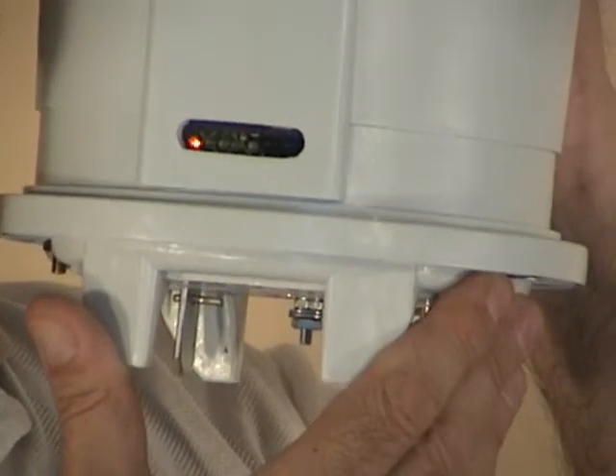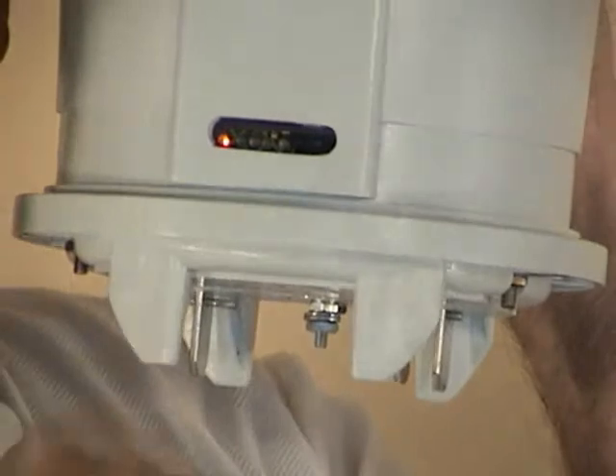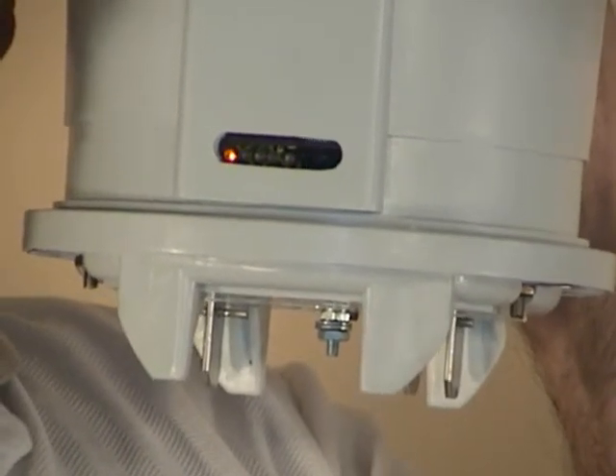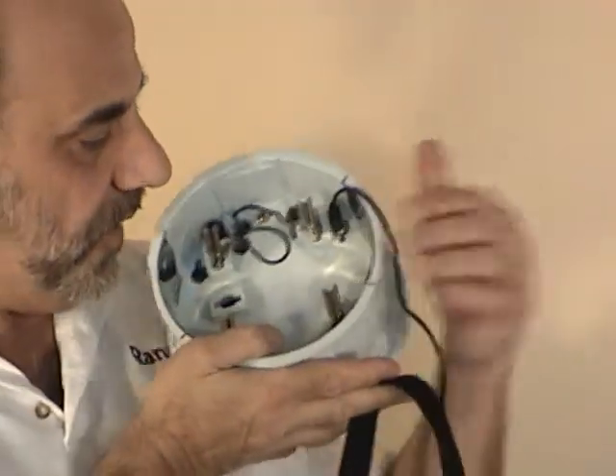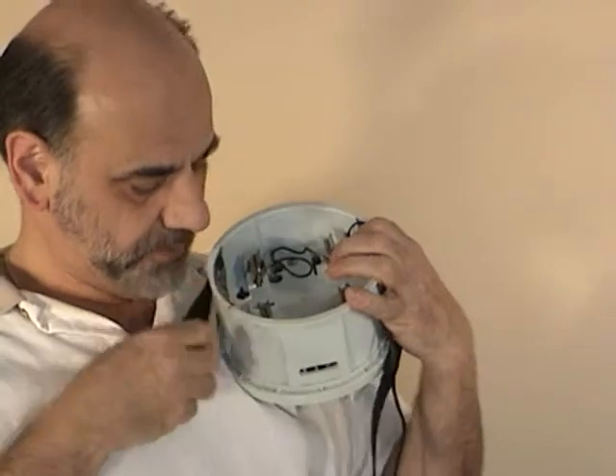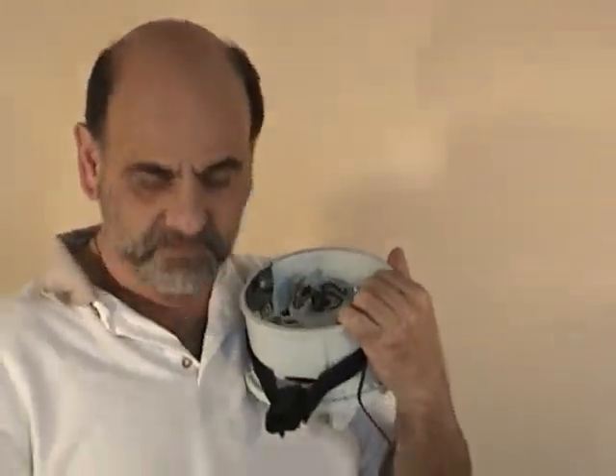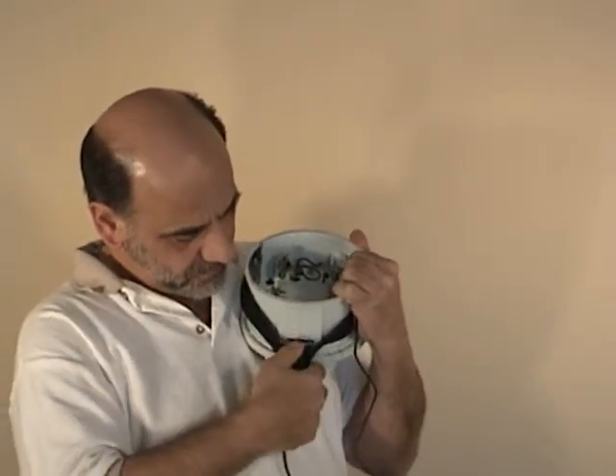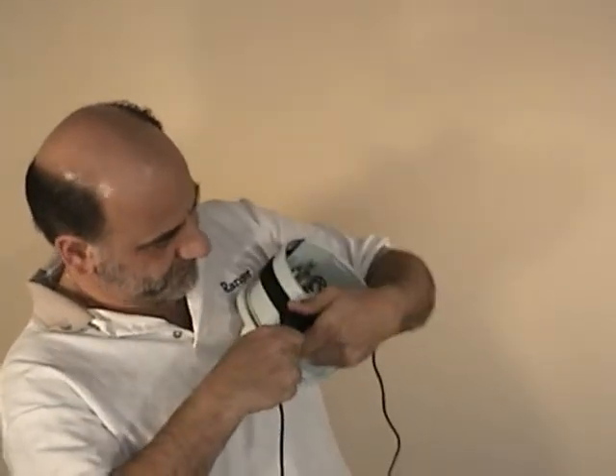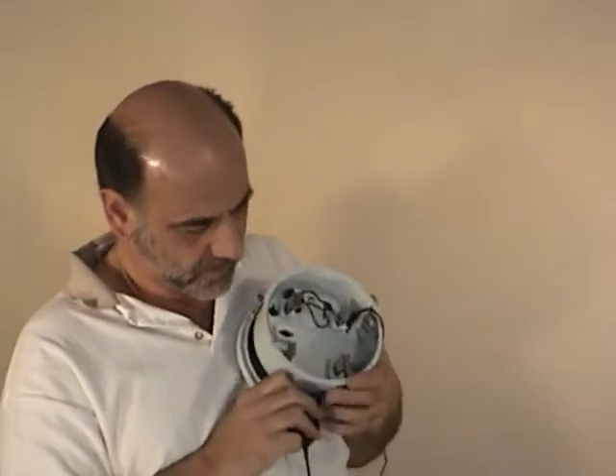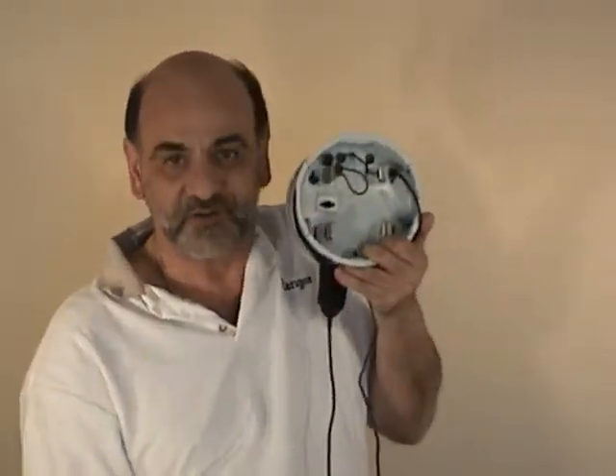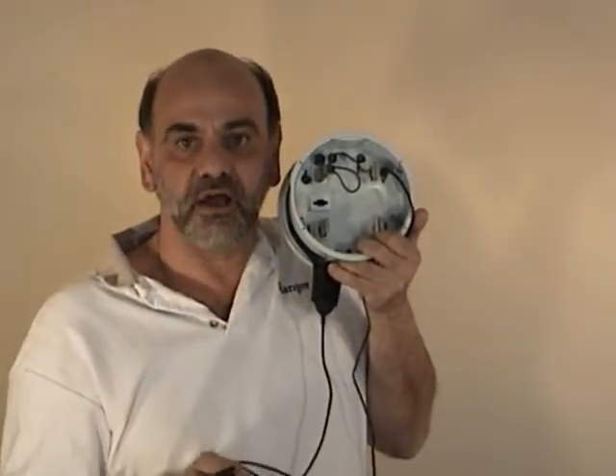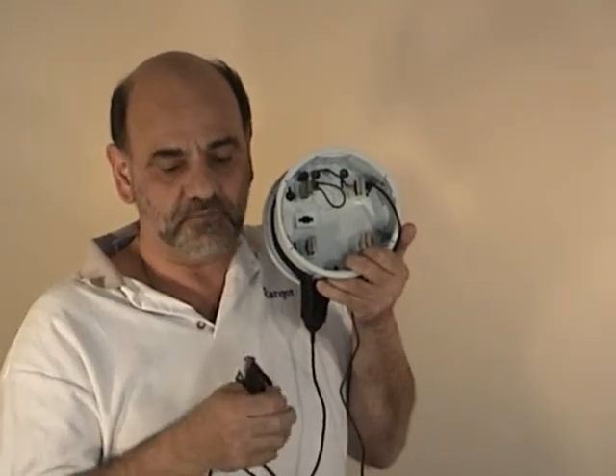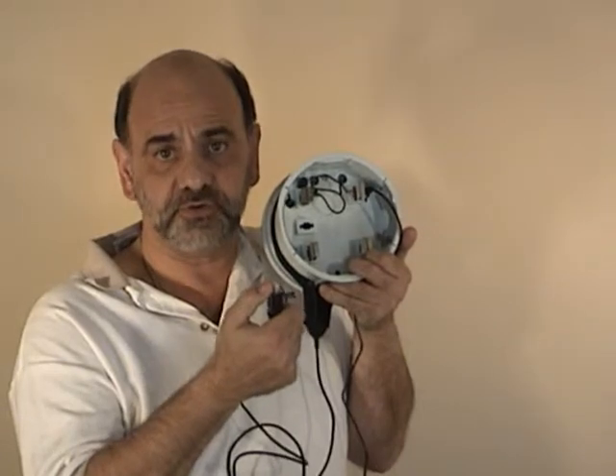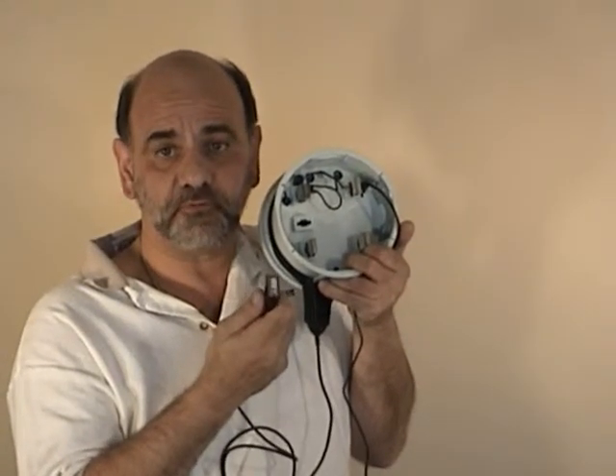This is also the area where you will pick up the infrared communication. Let me show you how you would do that if it was time to download a unit or program a unit. We have this collar that we showed you earlier, and the way this will work is it's velcroed, and you'll just basically put it around the unit like this. You'll take the infrared sensor, it just pushes right into the unit here. Get this down here, and it hangs right here at the COM port. This would be sitting on your desk, and then you would take the 9-pin D-sub, plug it into the port on your computer that you're doing the downloading in, or if you need to, like I mentioned earlier, you can get an RS-232 to USB converter, and that would be about $30 or $40 just about anywhere.